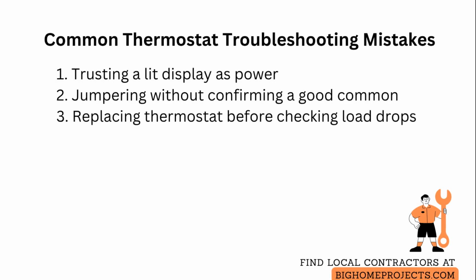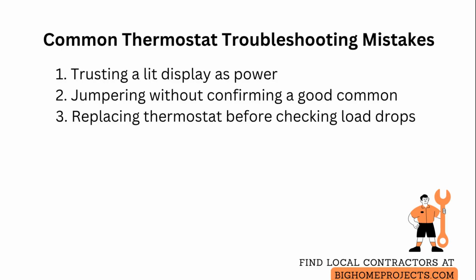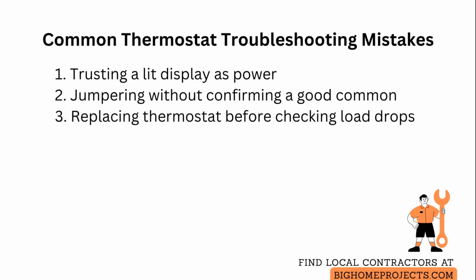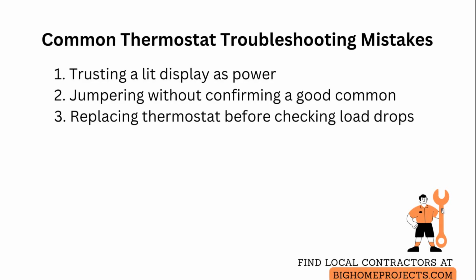The second is jumping R to Y or R to W at the thermostat without confirming a good common, which can hide an open common path.